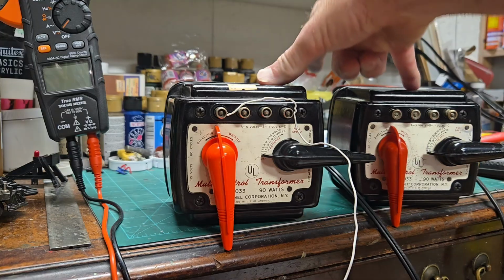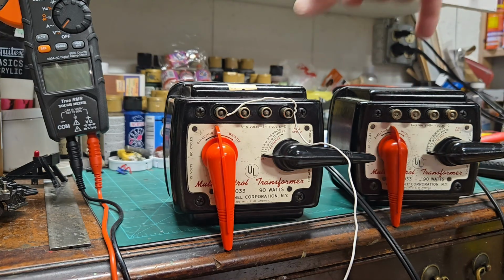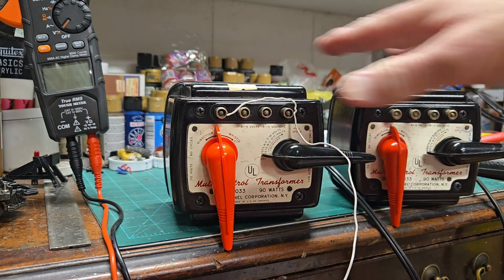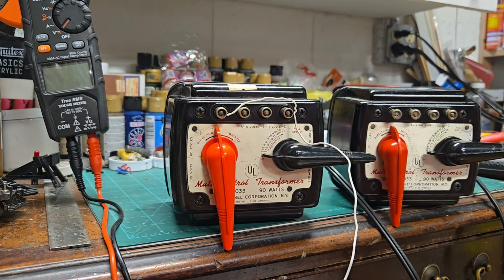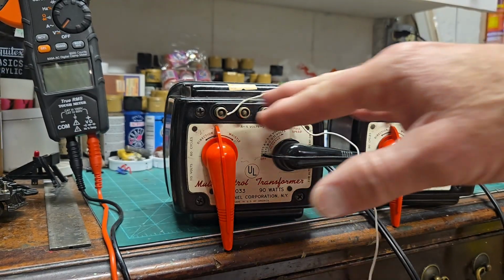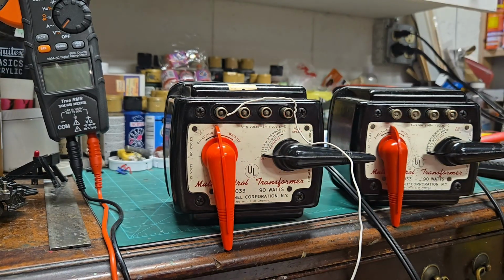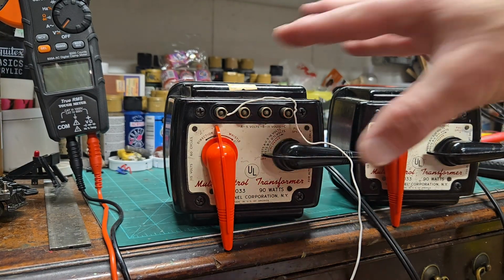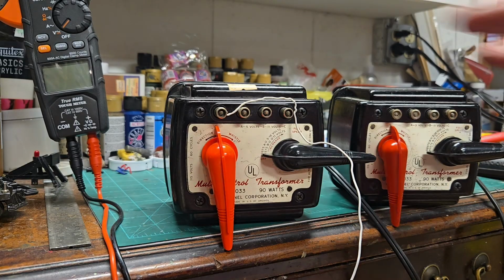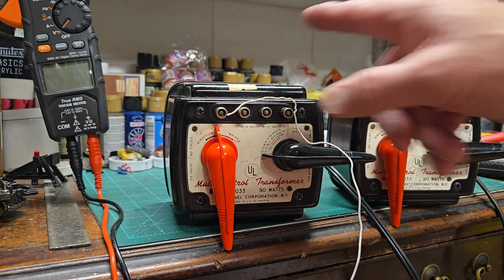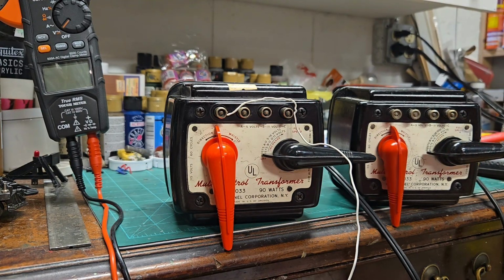I would recommend doing a visual inspection on these if you're trained to know what to look for. I rely heavier on that than anything else. Then also take a meter and check these voltages out - you certainly want to do that. Do a visual inspection, see if somebody's been in there monkeying around with it like I just did. If you're trained, I would know if I've been in this.